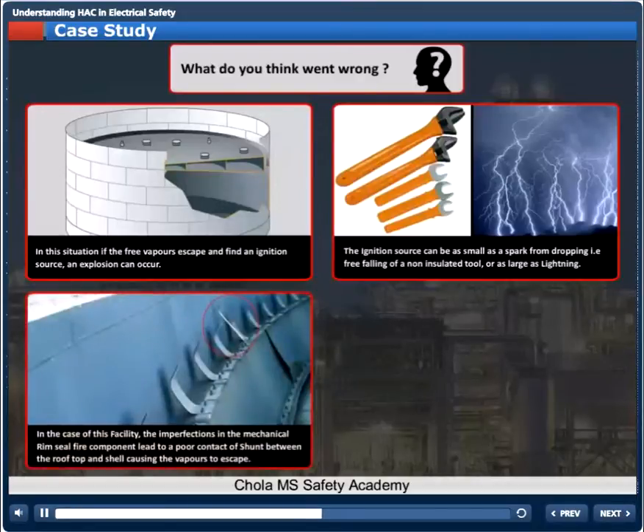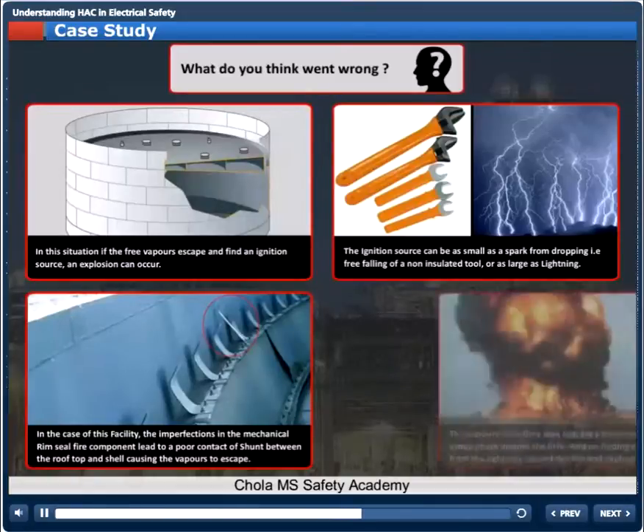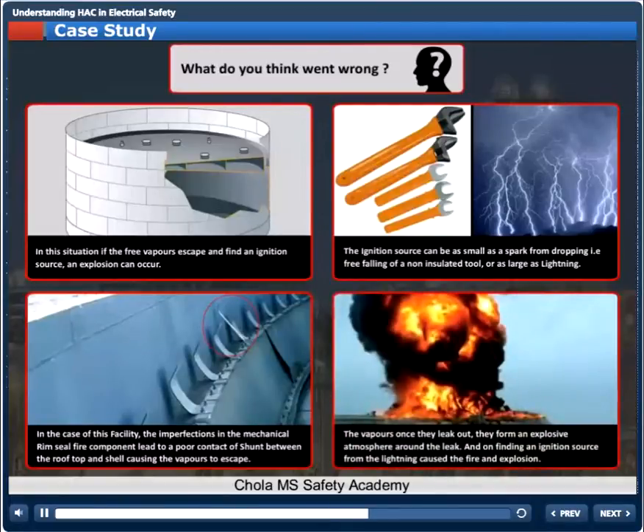In the case of this facility, the imperfections in the mechanical rim seal fire component led to a poor contact of shunt between the rooftop and shell, causing the vapors to escape. The vapors, once they leak out, form an explosive atmosphere around the leak, and on finding an ignition source from the lightning, cause the fire and explosion.